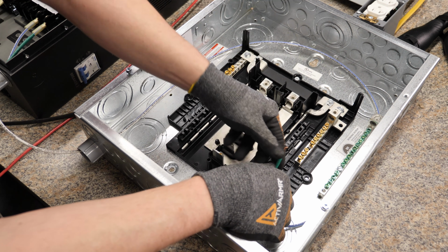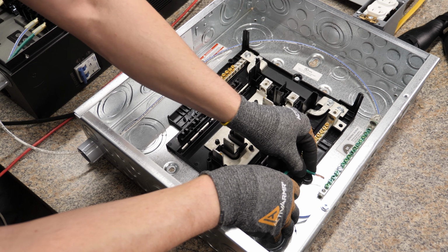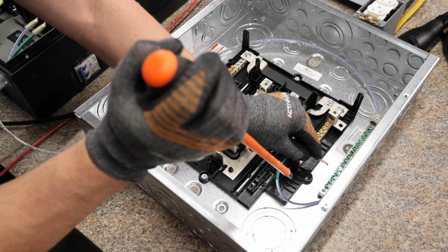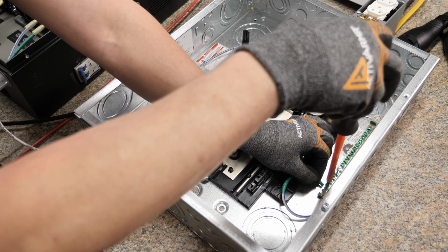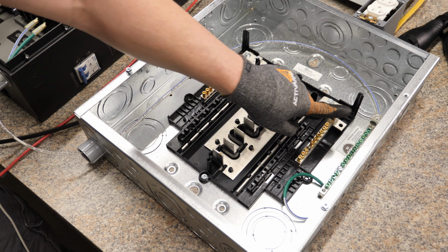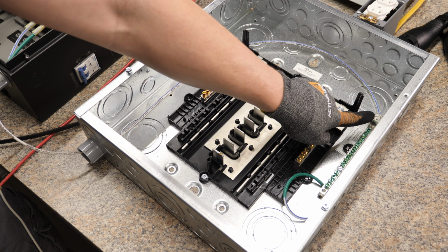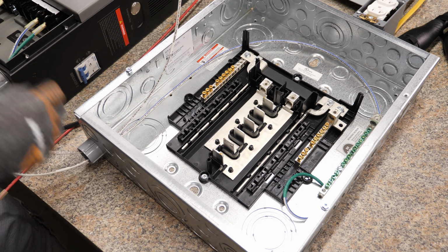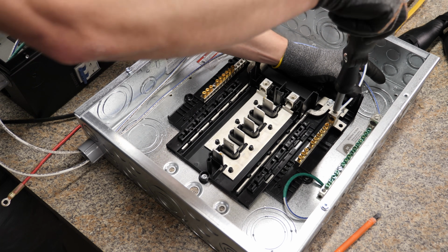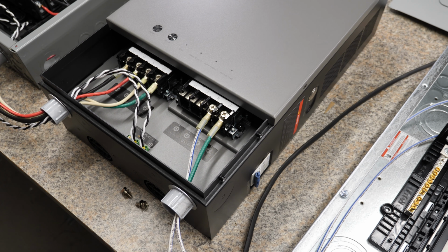Since this wire is kind of long, I'm going to loop it back around to the bottom side and go through one of these screws right down here. If we were using bigger wires, I would definitely use the main lug right up here. Next wire is the neutral, and then L1 and L2.